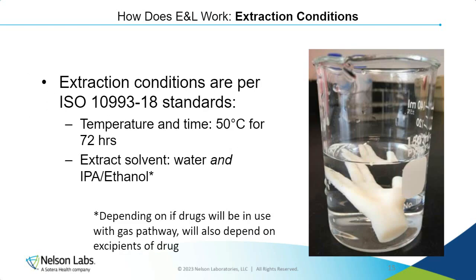These extraction conditions, as outlined in 10993-18, are where the device is extracted by being fully submerged, much like this hand and this beaker. Devices are normally extracted for 72 hours at 50 degrees Celsius. Mostly, the devices are extracted in water. However, if there is a patient's rebreathed air or drug excipients that may come into contact with the device, ethanol, IPA, or hexane may also be used as an additional extraction solvent, if they're compatible.